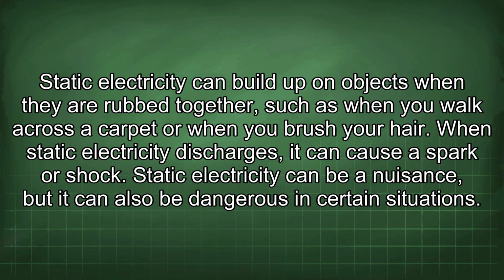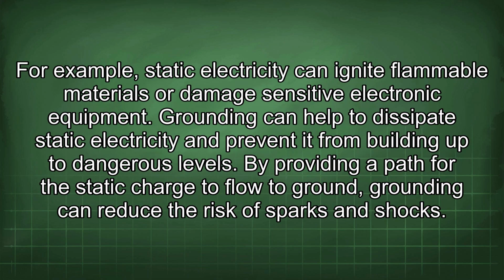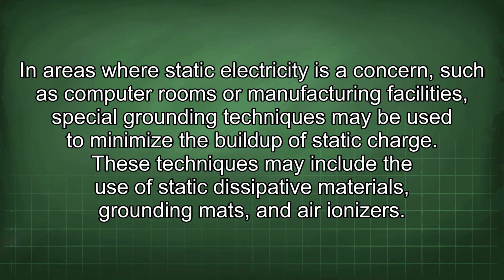Static electricity can be a nuisance, but it can also be dangerous in certain situations. For example, static electricity can ignite flammable materials or damage sensitive electronic equipment. Grounding can help to dissipate static electricity and prevent it from building up to dangerous levels. By providing a path for the static charge to flow to ground, grounding can reduce the risk of sparks and shocks. In areas where static electricity is a concern, such as computer rooms or manufacturing facilities, special grounding techniques may be used to minimize the buildup of static charge.